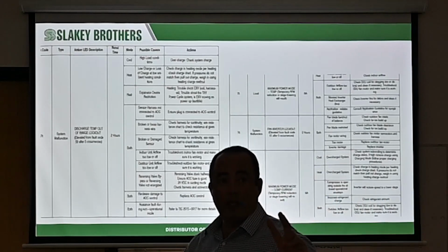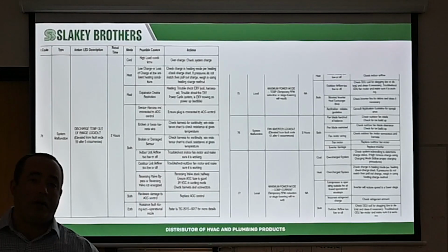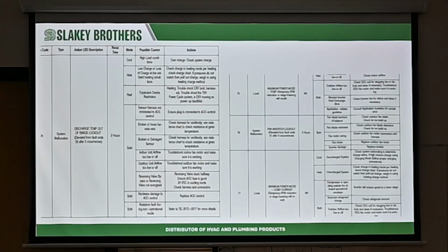Now remember, on these two units, the 5-stage or the Evolution Extreme, they are a variable speed three-phase motor. They're no longer a standard compressor. It's a 3-phase compressor, so you're checking readings. You go across these two, and these two, and the readings should all be the same. If one of the readings is really, really goofy, you've got a bad compressor. And if you ever get to that scenario, you're going to ohm out a condenser fan motor. If it's giving you a fault, you ohm out the condenser fan motor, and the numbers don't add up to what the book says they should for a set temperature. If it's nowhere near it, especially if the numbers don't add up, because all the windings should be equal. If they're not, you've got a faulty motor, you've got a faulty compressor.